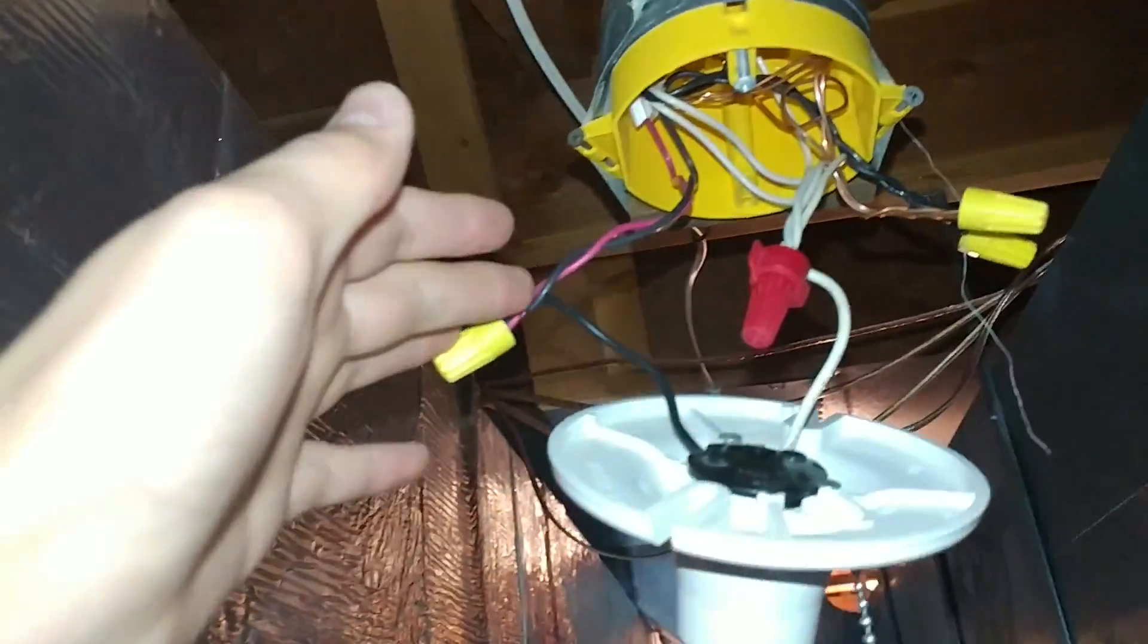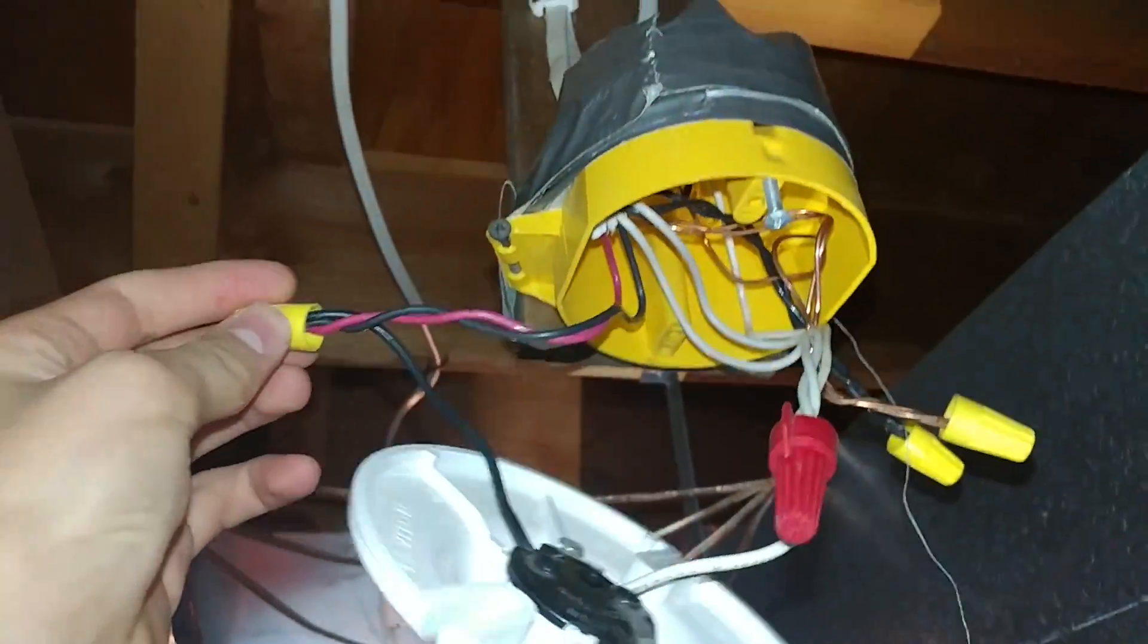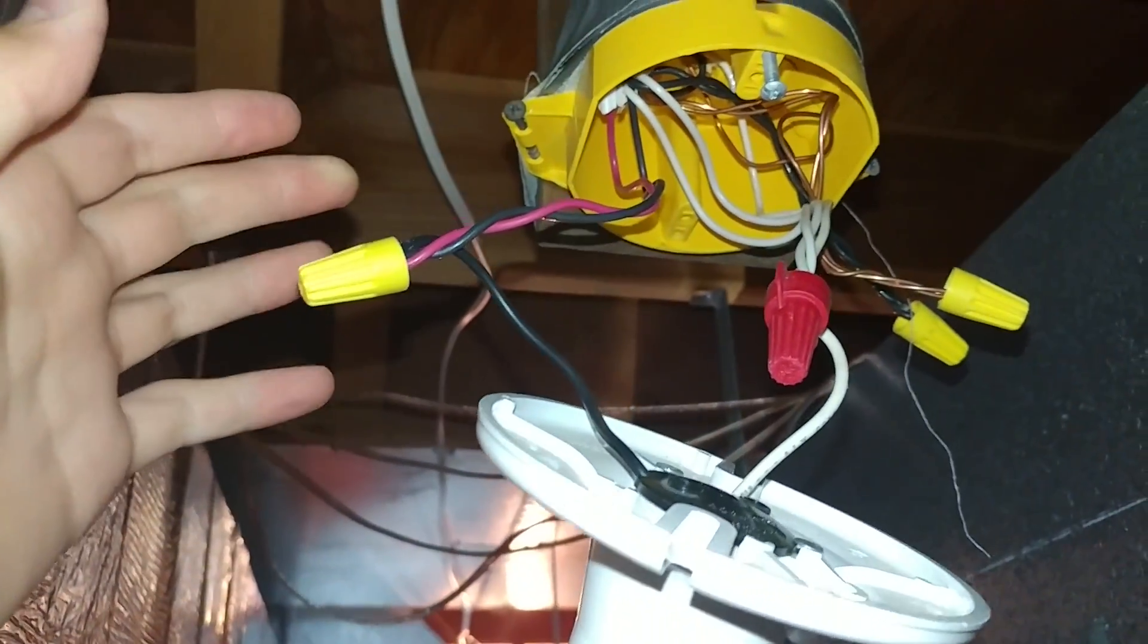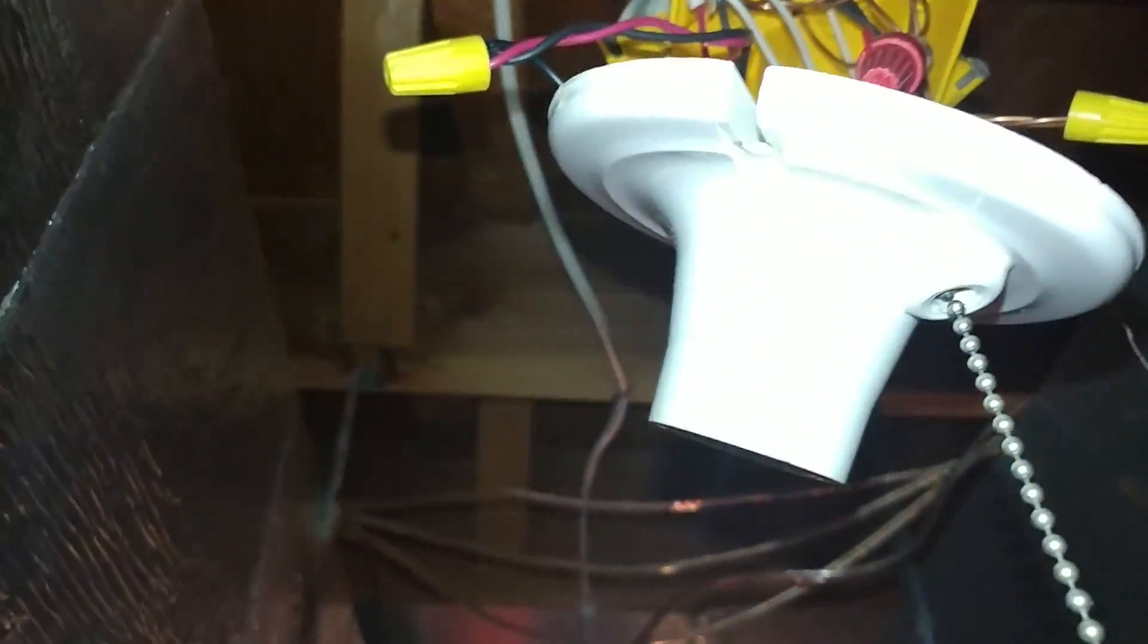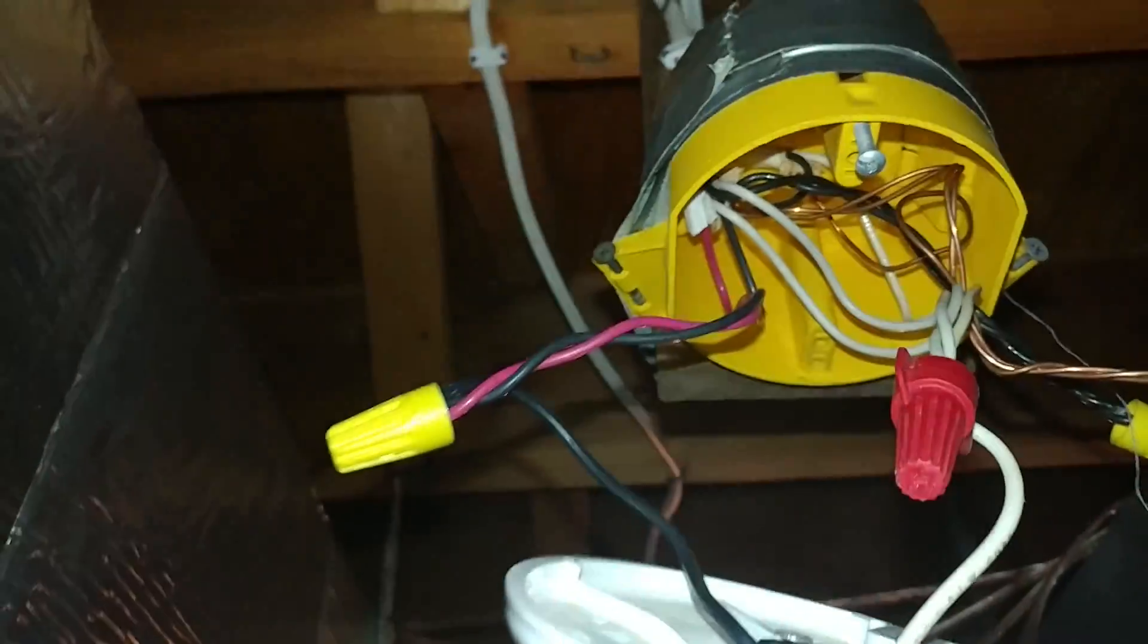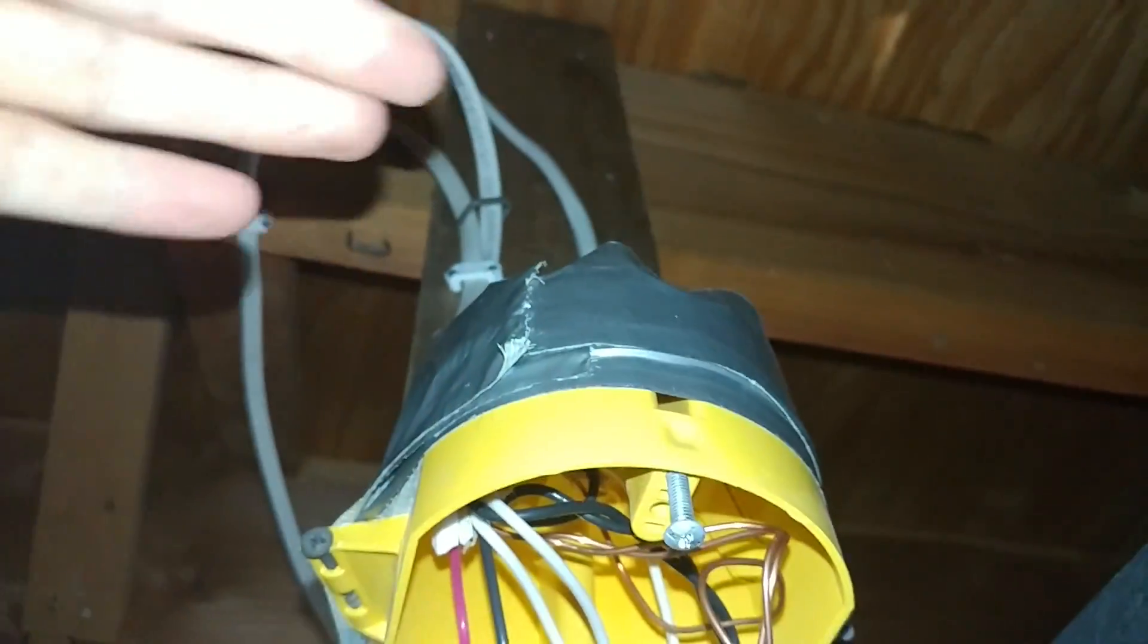So I used a 14-3. It is code now to have a switch to have a neutral in the box. But in a basement, unfinished basement, it's okay to use a 14-2, but I used a 14-3 so I could have a neutral. So that's how it works here. We have three wires. We have our feed coming in from the panel, we have the feed going out to that light switch, and we have a feed coming in from our switch.